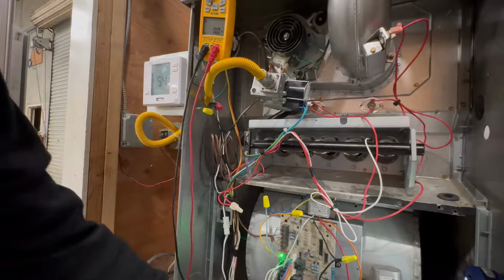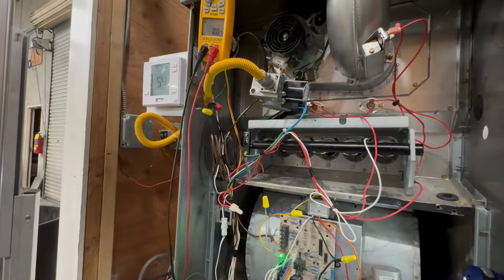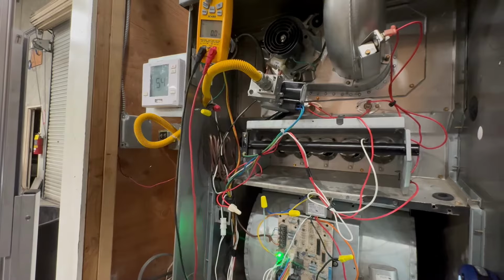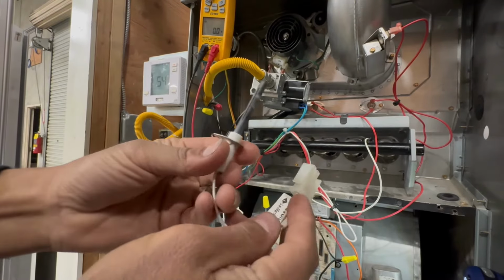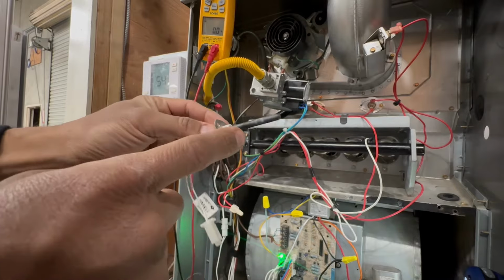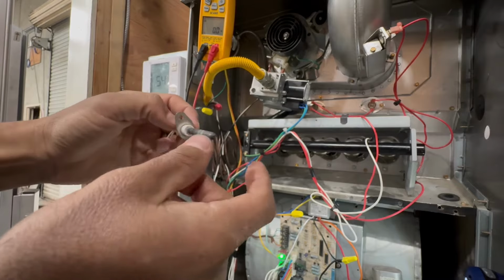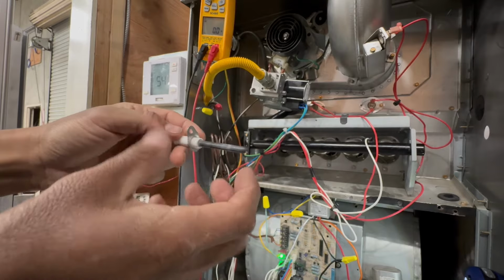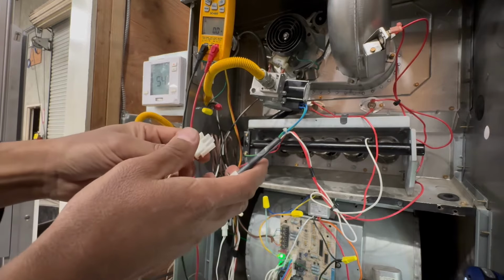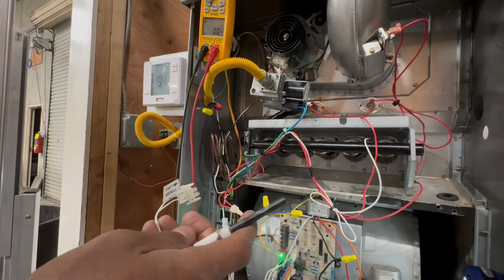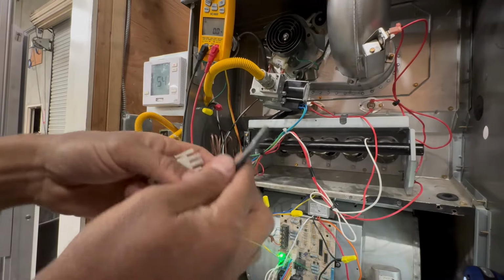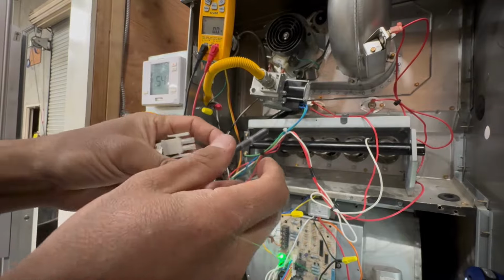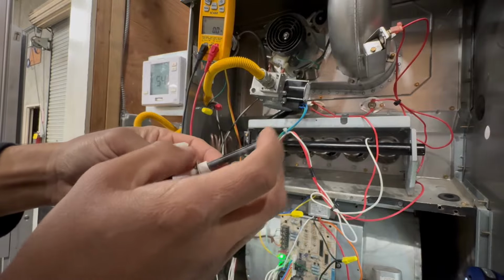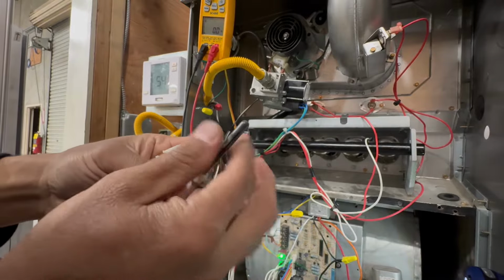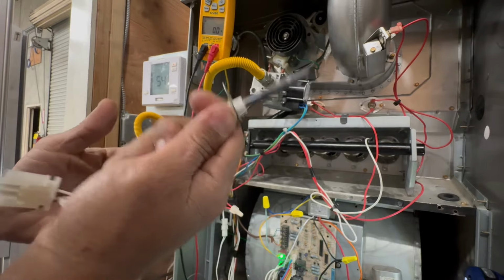And so we're not going to talk too much about the spark igniter. I'll do another video on that at a later date. But the hot surface igniter looks like this. When you buy a new one, you want to make sure you don't touch this part. Now, this one has been touched by a lot of the guys that sometimes just grab it, and this one is used for demonstrations, just to test it. So this one's been touched a lot, but the idea is that when you buy a new one, you don't touch this part because the oils in your hand will disrupt the function of the hot surface igniter. So you want to be careful not touching this with your hand. Just touch it from here.